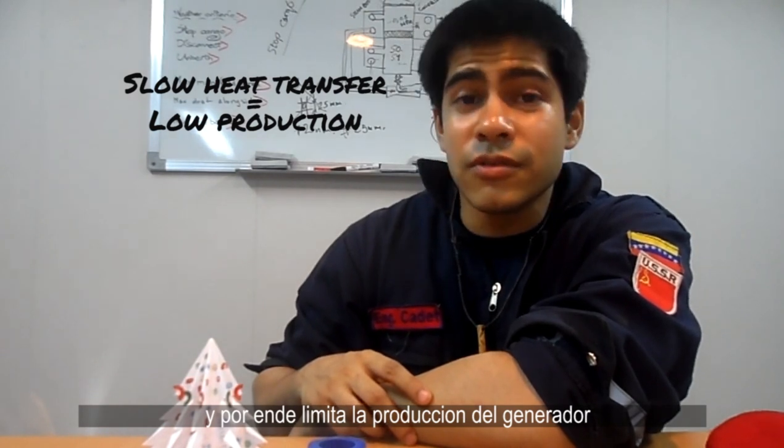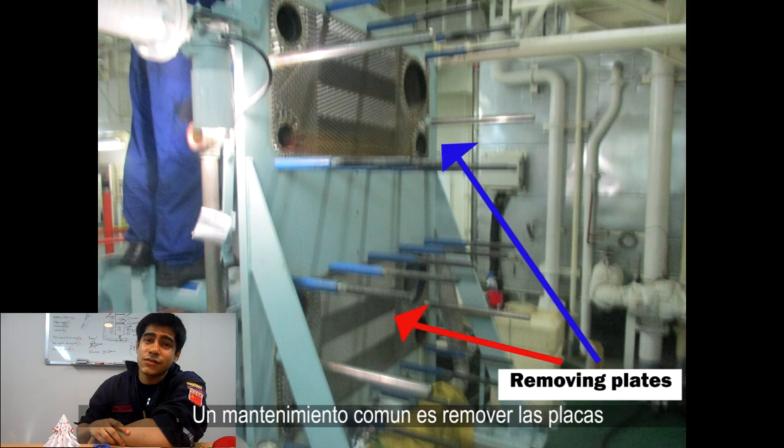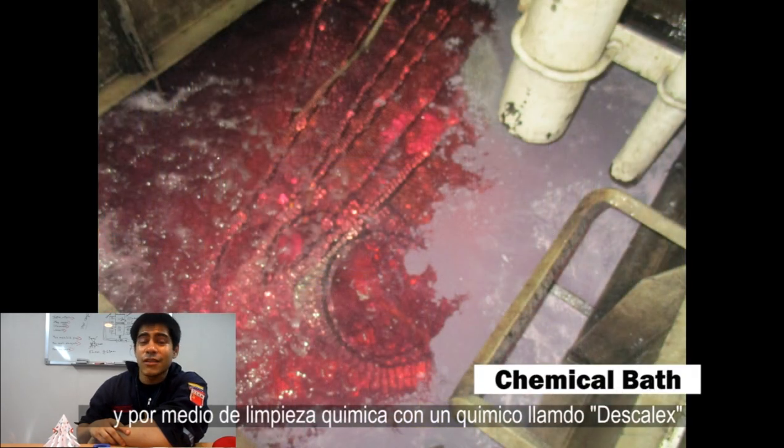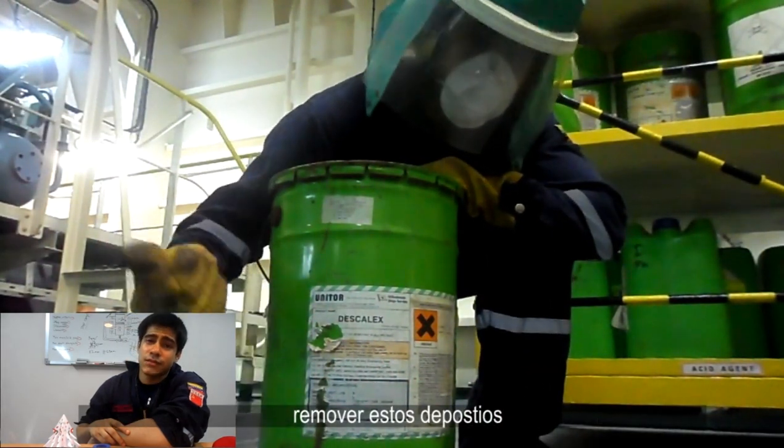Salt deposits in the plates will slow down the heat transfer from the jacket water to the seawater and therefore limit the production. A common maintenance procedure is to remove the plates and through chemical washing, with a chemical such as Descalex, remove these deposits.